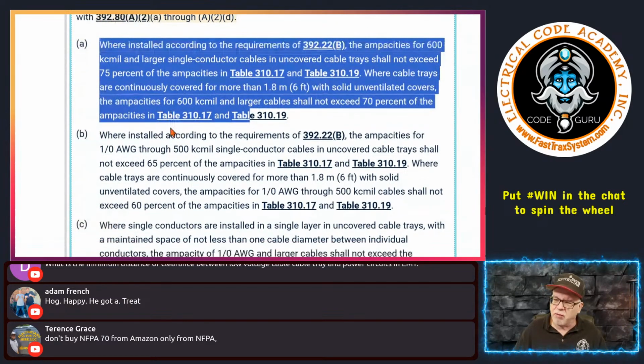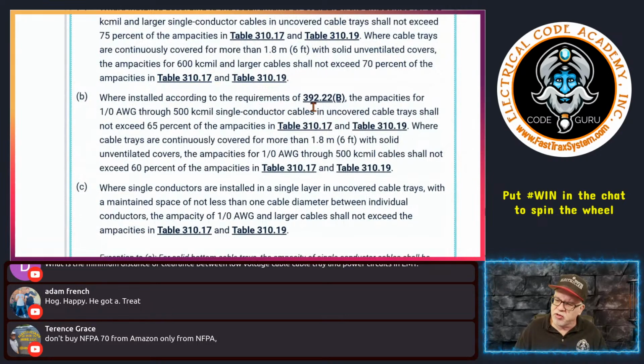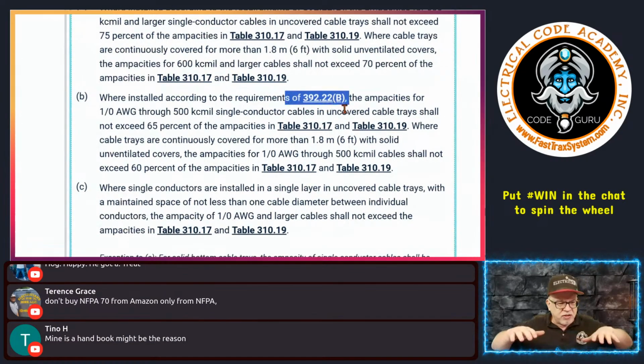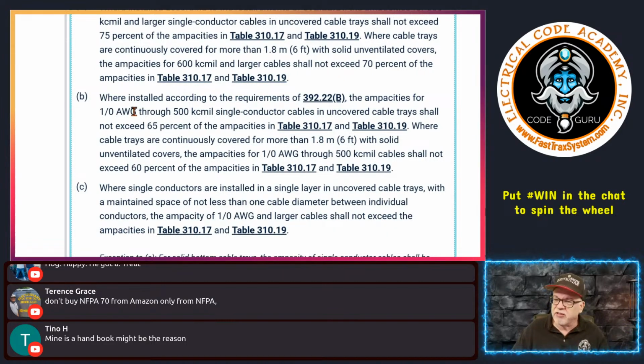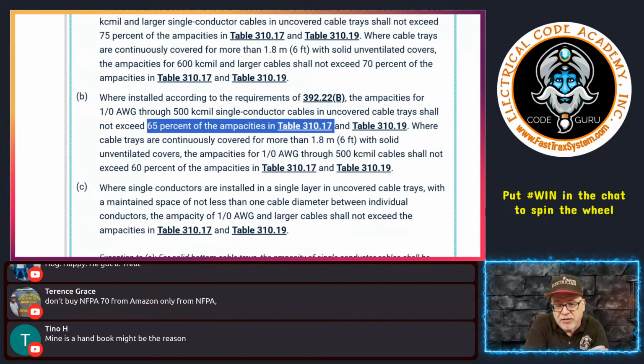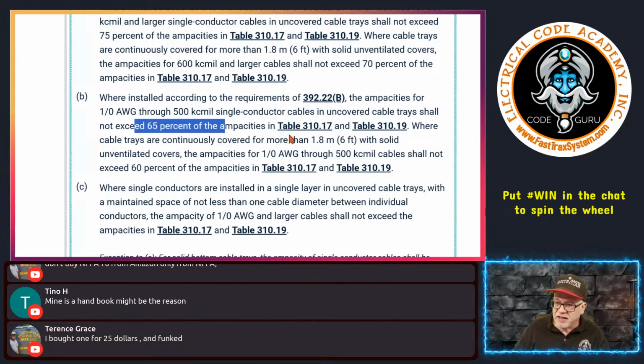Now, what about other sizes? Well, we're installing according to the requirements of 392.22(B) again, so assuming you're putting these conductors in there. Now, your handbook should be exactly the code. The commentary is different, but the code part, not the blue part in the handbook, should be exactly the same as the code book because they're both from NFPA. If your code portion is different, you've got a counterfeit book, my friend. All right, so now we're installed in accordance with these requirements. The ampacity for 1/0 through 500 kcmil single conductor cables in an uncovered cable tray shall not exceed 65% of Table 310.17. So you see why we do not have to worry about 310.15(C)(1) here? Because you're already reducing the ampacity of these conductors.